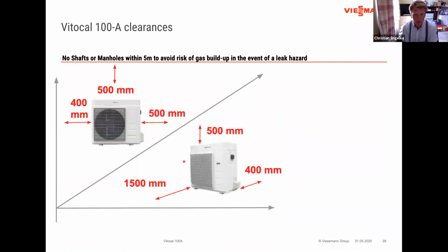Clearances, again, are one of the things that need to be observed. With the outdoor unit, it is required to maintain some form of minimum clearances. We do see that customers would like to hide the machine in boxes or wooden sheds built around it. But please make sure, if that's done, that there are still clearances around it, so installers and service engineers can easily work on these machines. And these are the minimum clearances we recommend. Also to the top, about half a meter, and to the sides, that should be sufficient to allow people to work on this machine safely.